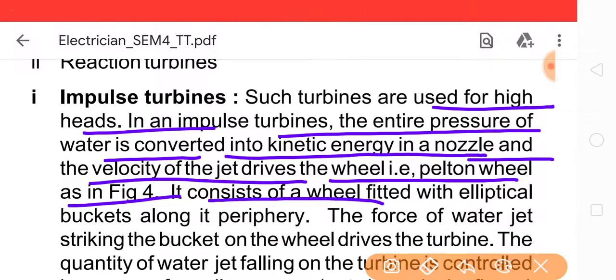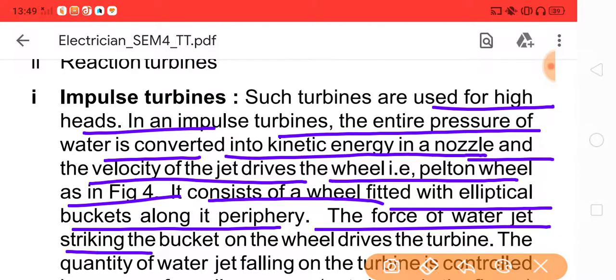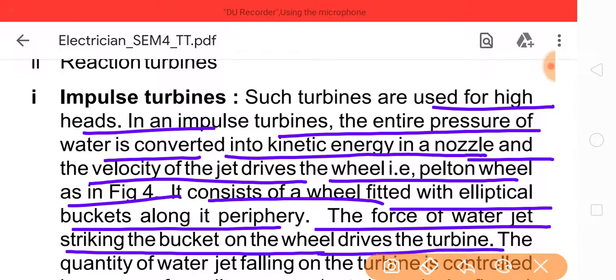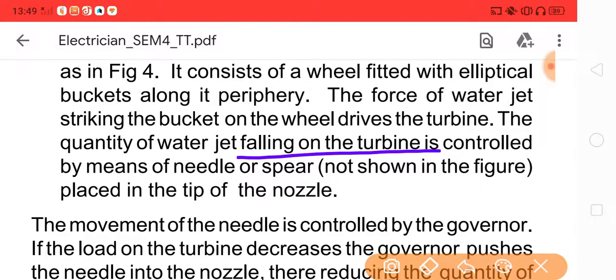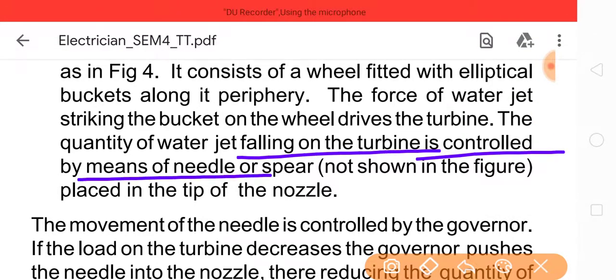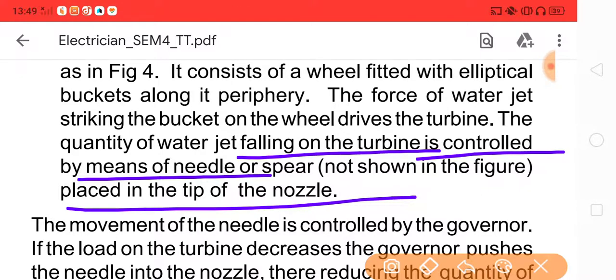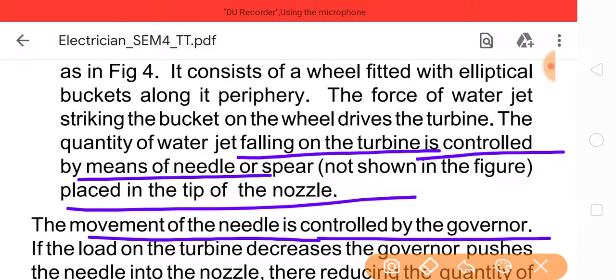It consists of a wheel fitted with elliptical buckets along its periphery. The force of the water jet striking the buckets on the wheel drives the turbine. The quantity of water jet falling on the turbine is controlled by means of a needle or spear placed in the tip of the nozzle. The movement of the needle is controlled by the governor.